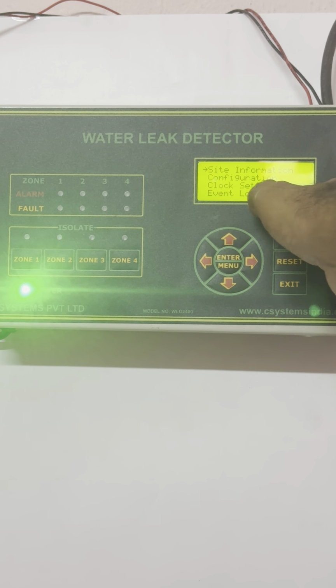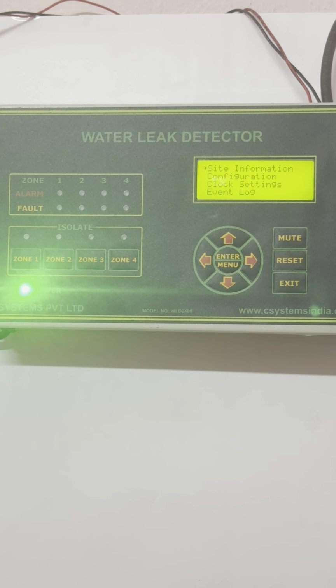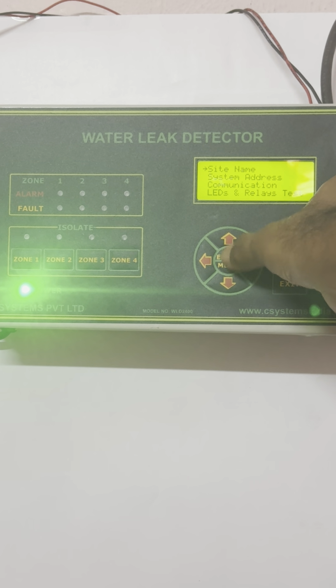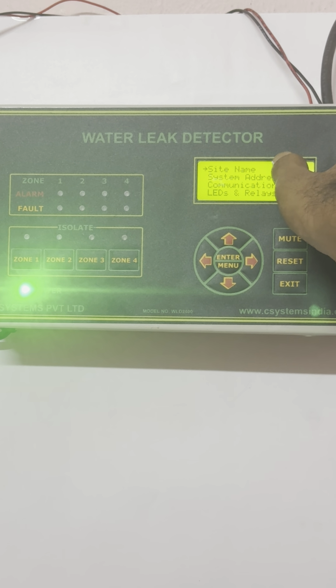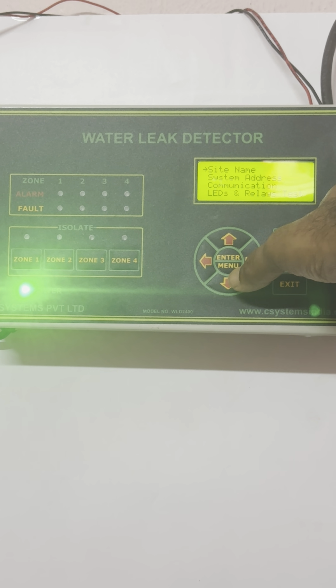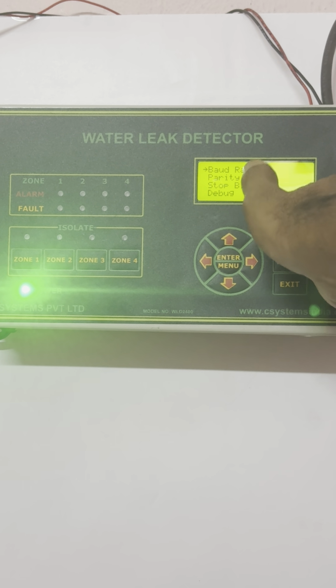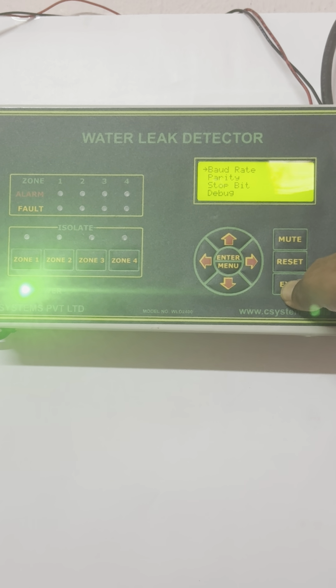So, site information, configuration, clock settings, event log. These are the four sub menus. Site information: you can type in the site name of the relevant site. System address is the address that has to be configured in order to integrate it with the BMS. Communication parameters can be modified in this menu: baud rate, parity, stop bit, and debug is our internal functionality. And this LED and the test facility relay test, I will explain you a little later.